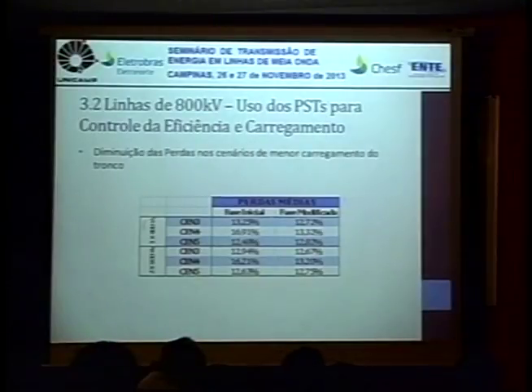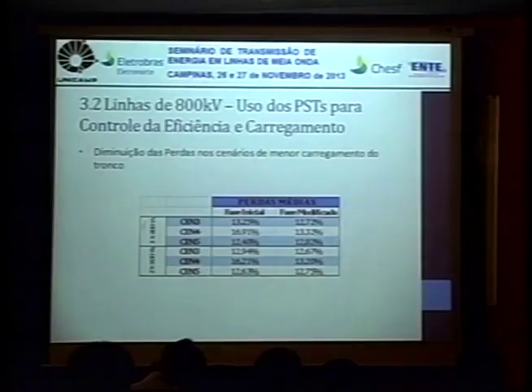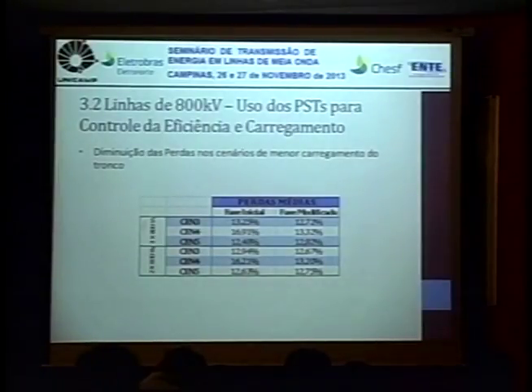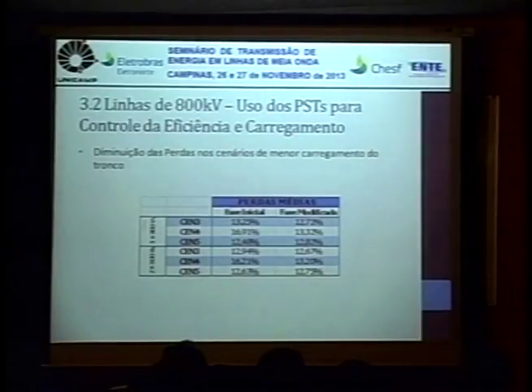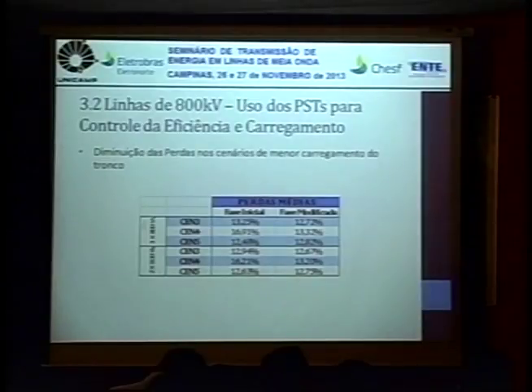the scenarios. So you can see all the scenarios here. This would be the losses of the line by just adjusting the tap, and here the losses on the line by also adjusting the out of phase. So for all the scenarios we could bring losses to these standards of 12 or 13% in all standards by adjusting both the tap and the out of phase at the end of the line.